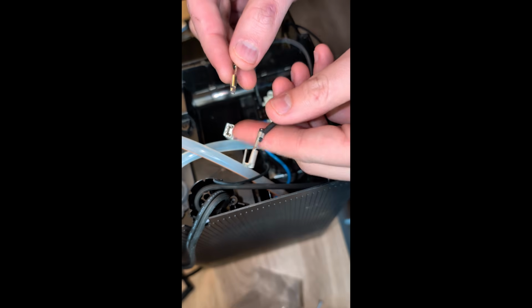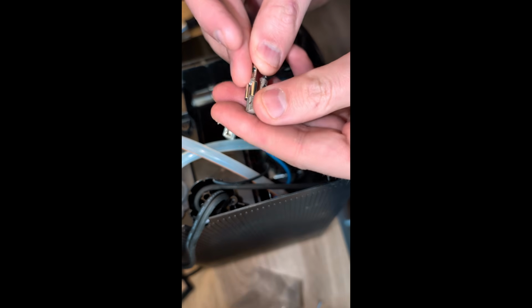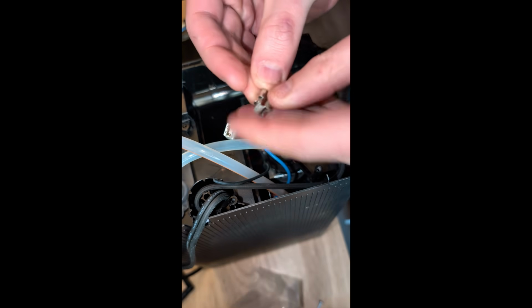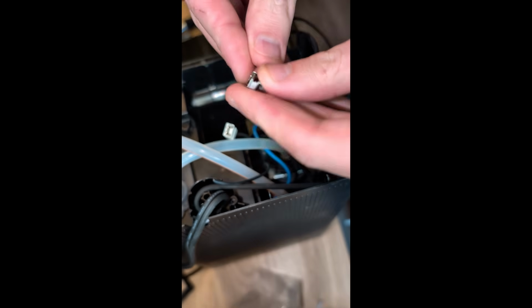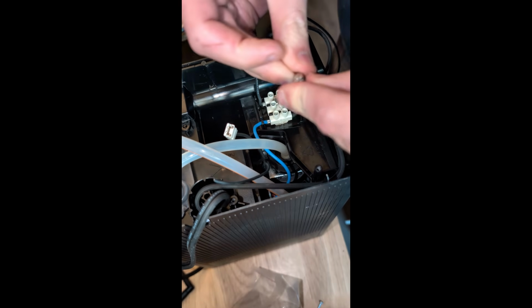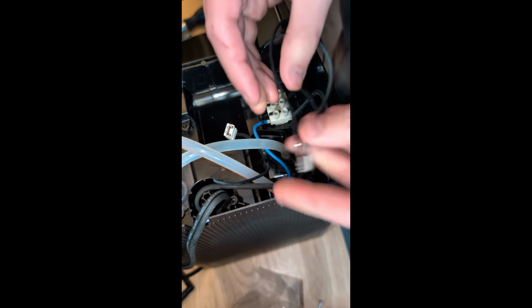So this is what the piggyback connector should have looked like. You need to make a new neutral cable, approximately 12 inches long, that will connect into this piggyback connector. This cable will be fished up to the top of the machine and will provide the neutral connection to the power cord.